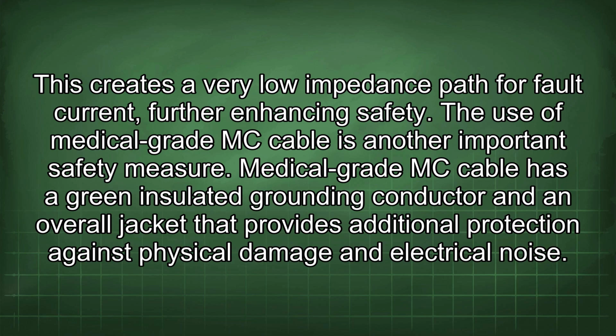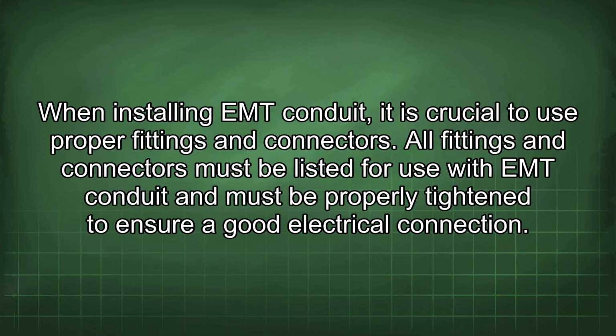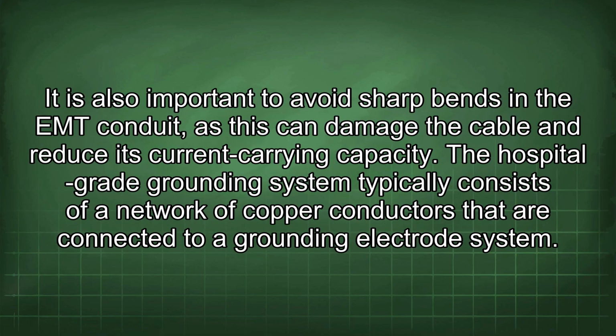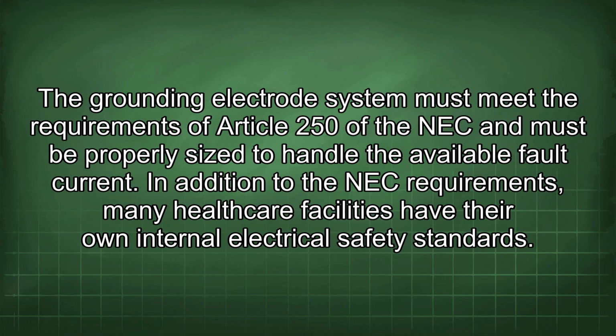and electrical noise. When installing EMT conduit, it is crucial to use proper fittings and connectors. All fittings and connectors must be listed for use with EMT conduit and must be properly tightened to ensure a good electrical connection. It is also important to avoid sharp bends in the EMT conduit, as this can damage the cable and reduce its current carrying capacity. The hospital-grade grounding system typically consists of a network of copper conductors that are connected to a grounding electrode system. The grounding electrode system must meet the requirements of Article 250 of the NEC and must be properly sized to handle the available fault current.